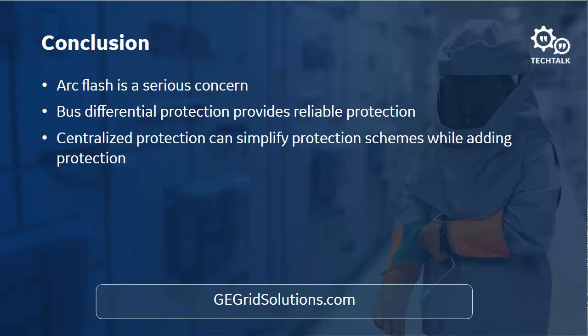There's a question: in the near future, only one box can have all the protection functions linked with MUs. Yeah, we do have that for bus and feeder protection. So it's one box. It has all the bus protection, all the feeder protection, reclosing, sync check, everything is available in the one box. And as a protection engineer, I'd say you probably have at least 2 for redundancy. Depending on the size of the station, you may have 3. That way you always have at least 2 relays, so if one of them goes down, you still have 2.